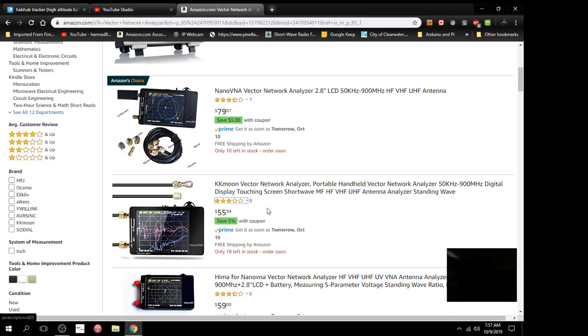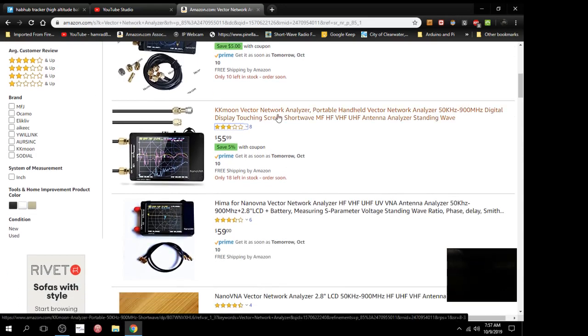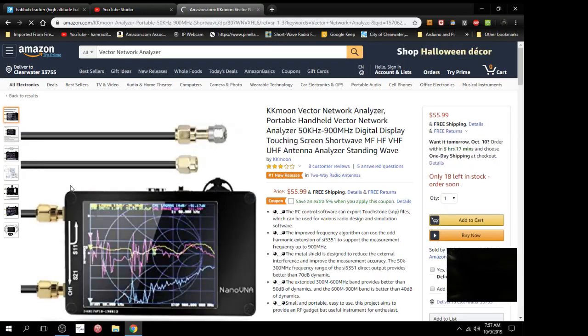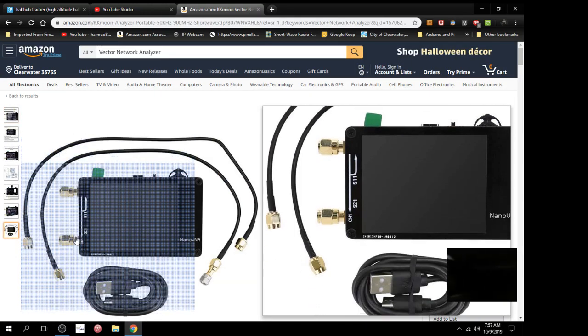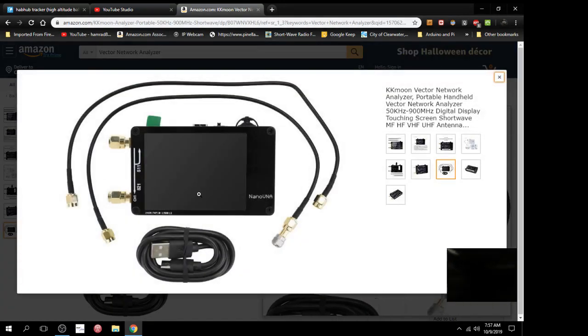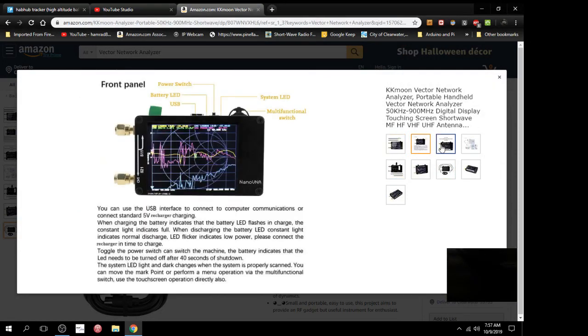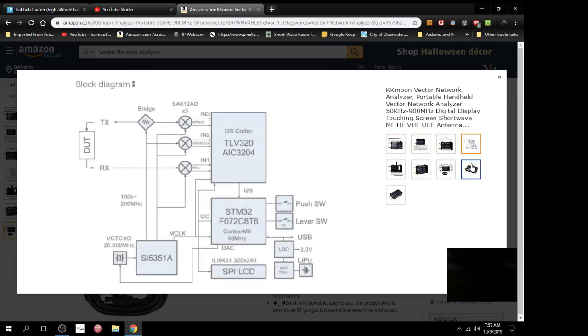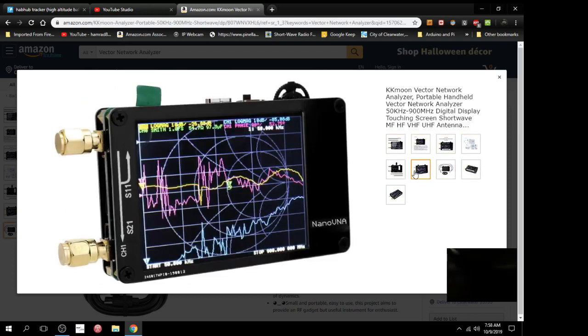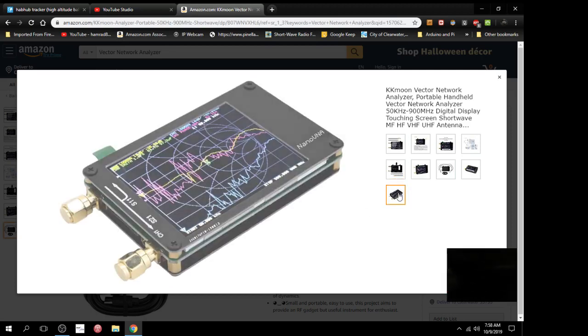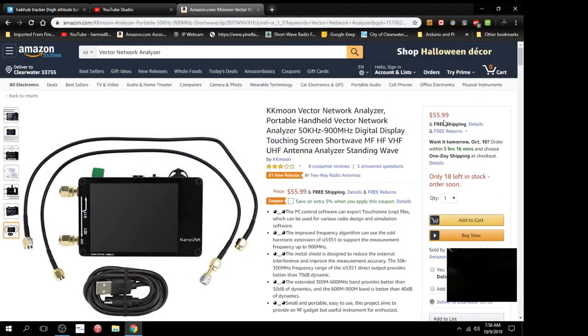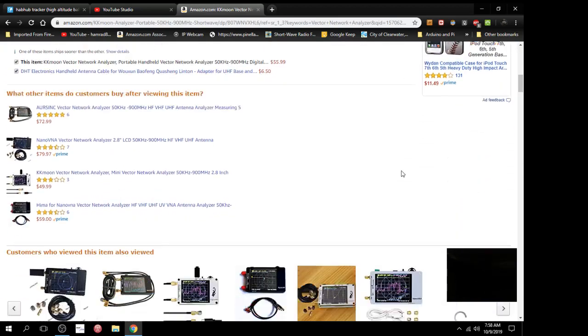Although it doesn't show in the picture here these little gizmos here. Let's go look. I didn't mean for this to babble so long. So this one does not appear to have those needed devices, those needed loads for calibration. But you'd want, you'd really want that. You want to get the whole smear. Now this shows a cable with something on the end of it. Why do they have to make it so darn complicated? And this shows the connectors with things on the end of it which could be the loads. There's a 50 ohm load, there's an open load, there's a short load, and then there's a pass-through.